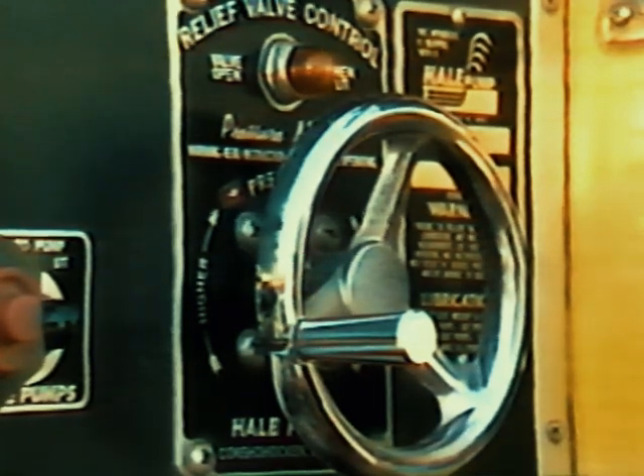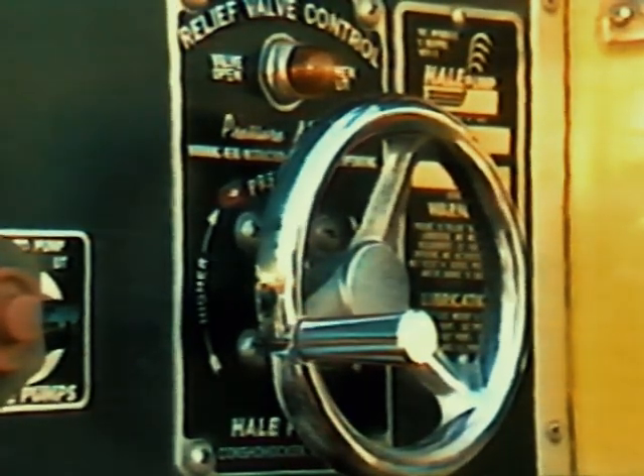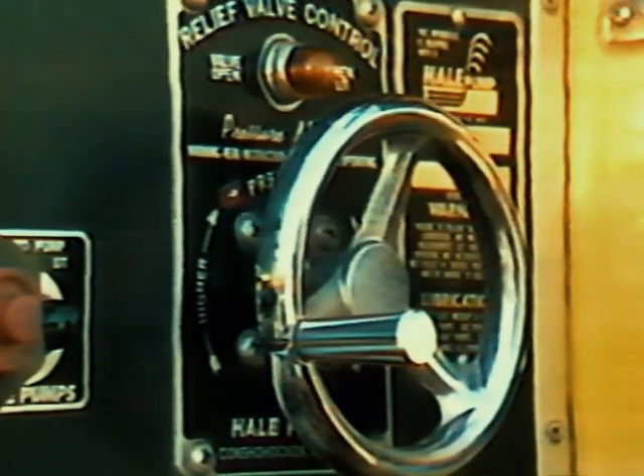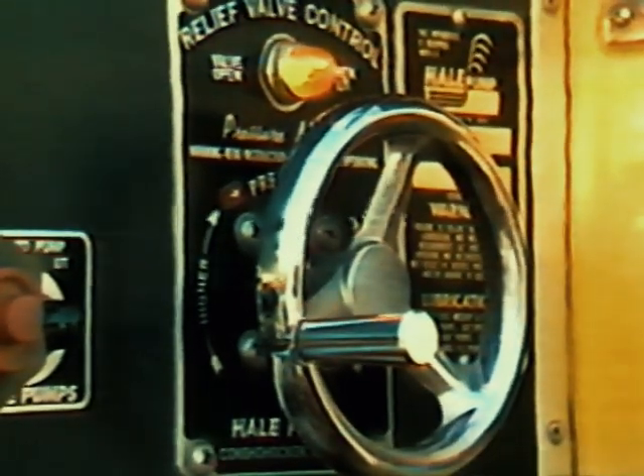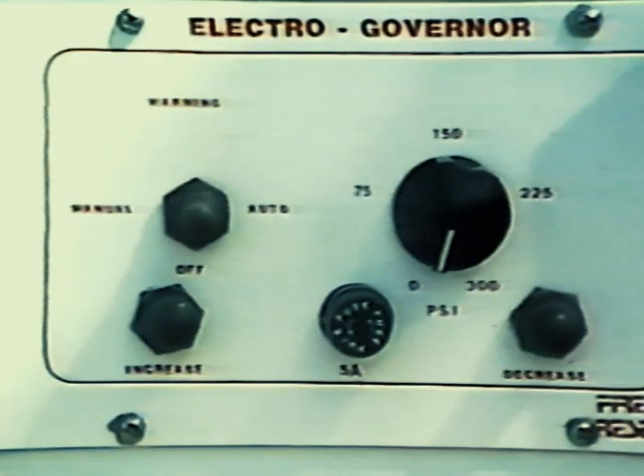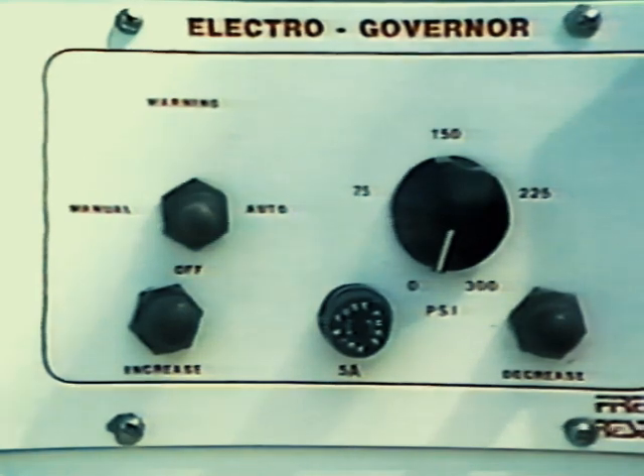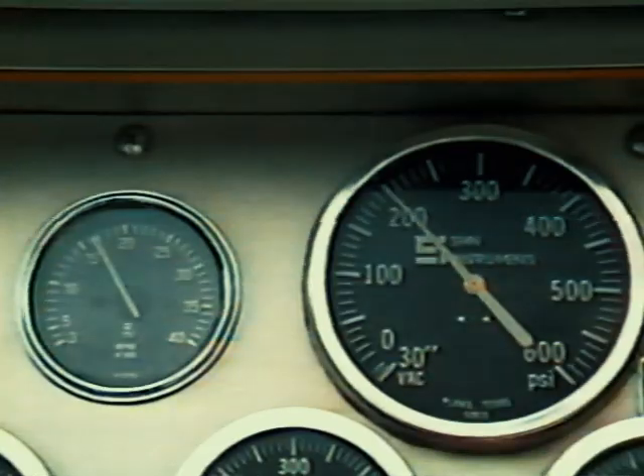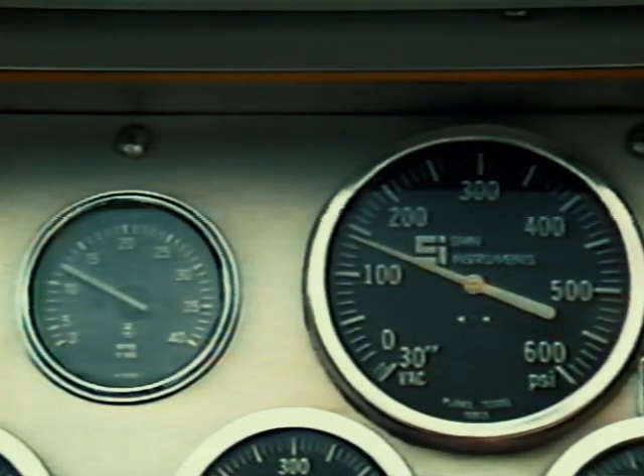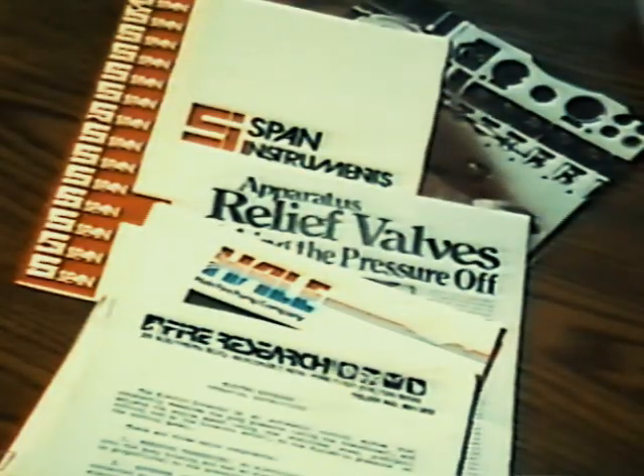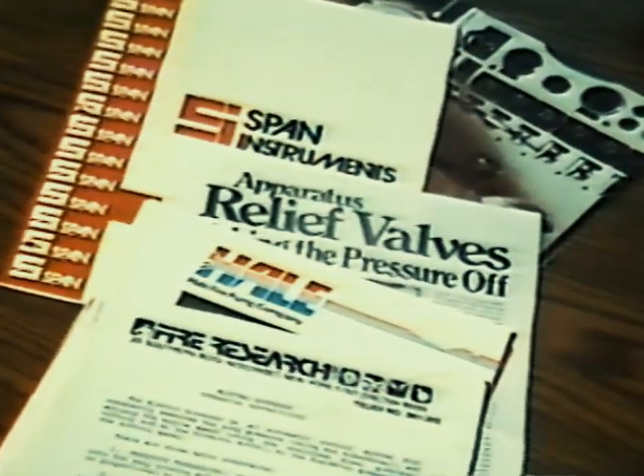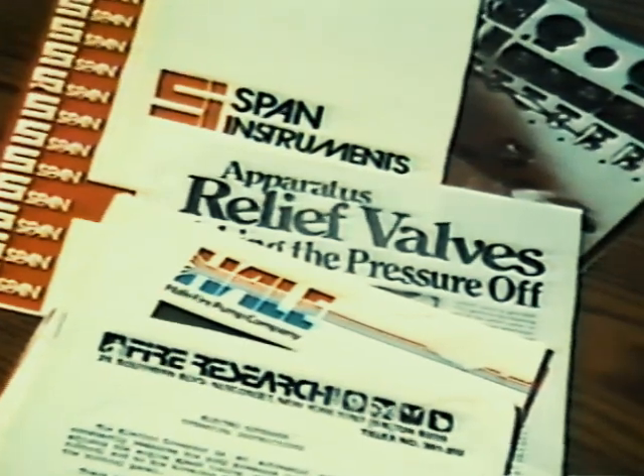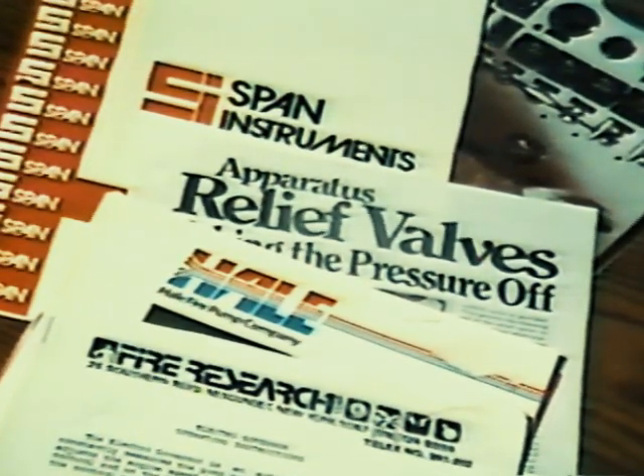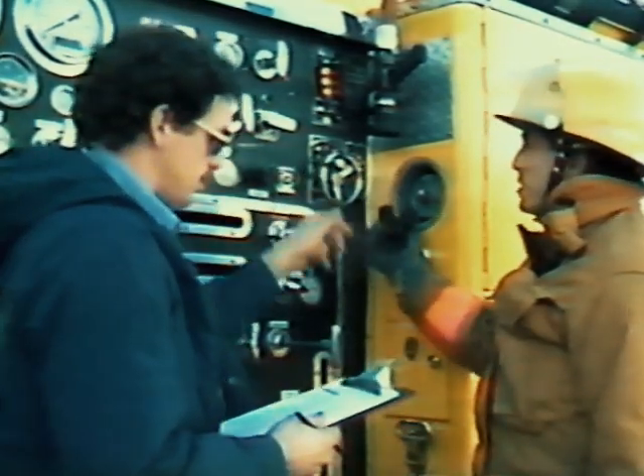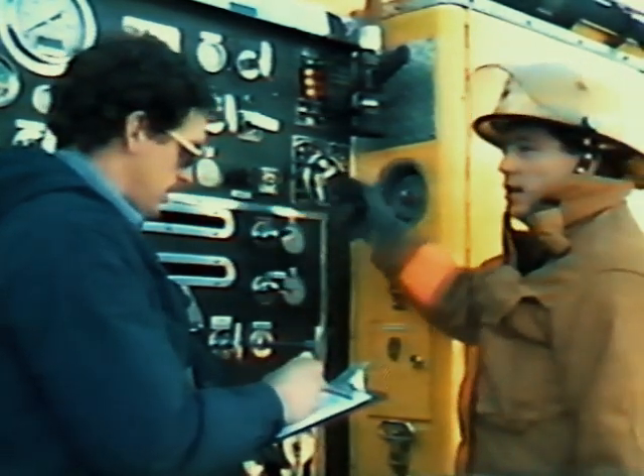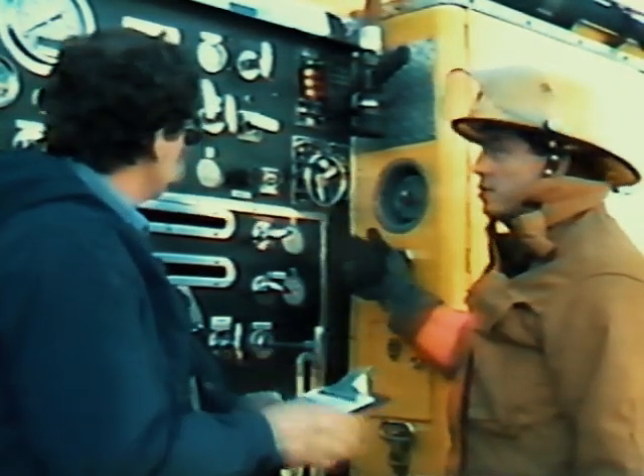To relieve excessive pressure, an apparatus is usually equipped with either an automatic relief valve that opens as a bypass between the suction and discharge side of the pump, or a pressure-operated governor that controls the speed of the engine to slow the pump and decrease the amount of water pressure. There are many different manufacturers of governors and relief valves, and many differences in the way each operates. As a pump operator, you need to become familiar with the pressure control device on your apparatus.